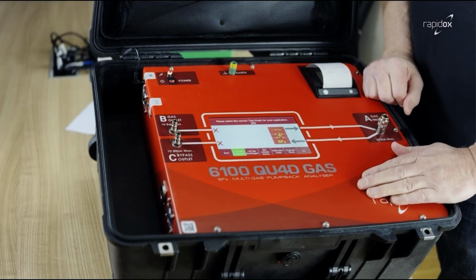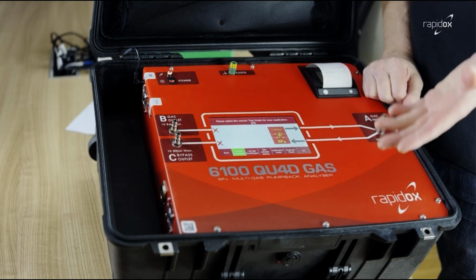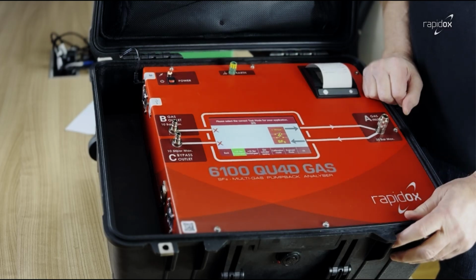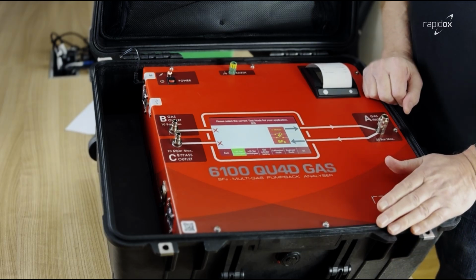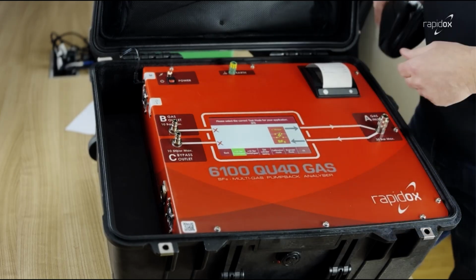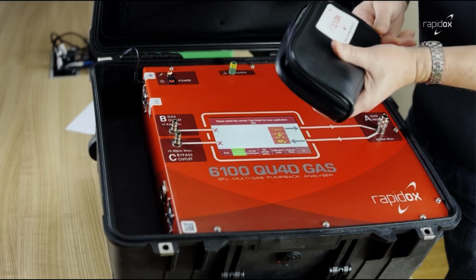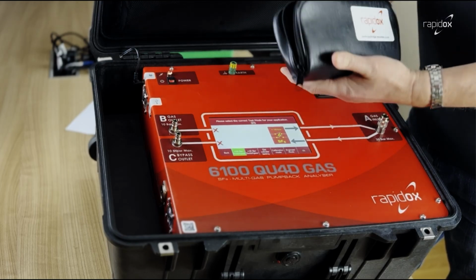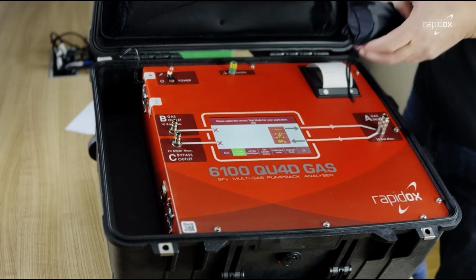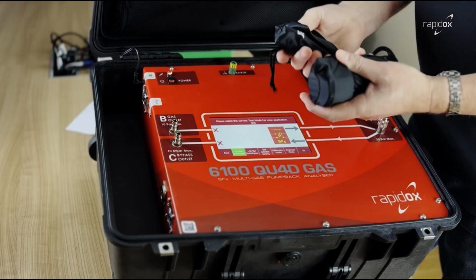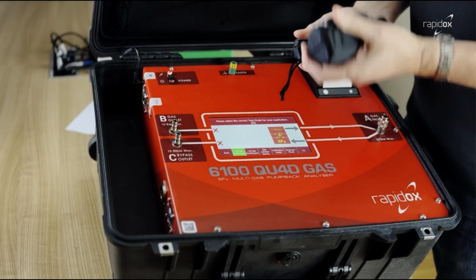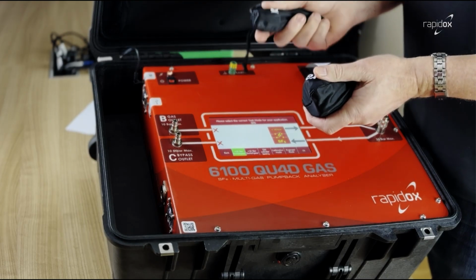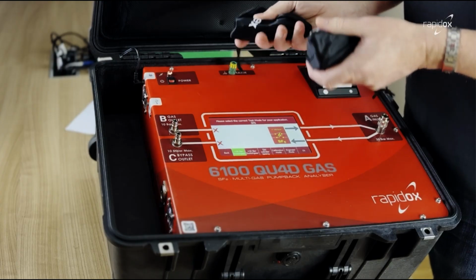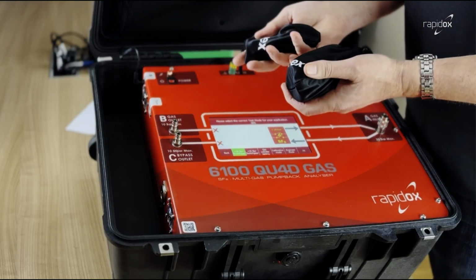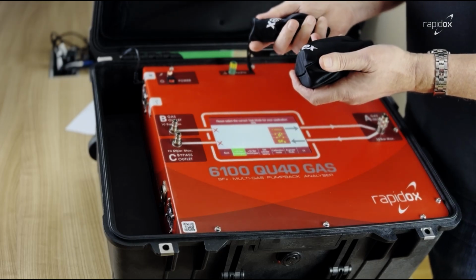The most important accessory of all are the couplings that you use to attach to the gas, the GIS, the circuit breaker or the transformer, and they are generally around the world often made by Dilo, or Delo, depending how you say it. And so we do supply genuine Dilo couplings here, and these are an option, but they are an option that most people include in their purchase, and they are supplied in a bag. And the two most common Dilo couplings that are used around the world are a number 8, DN8, and a number 20, DN20. There are, however, other couplings such as 6, 7, 12. These are much less common, but they are available from Cambridge Sensor Tech as an option in our coupling kit accessories. So I'll just open these up.